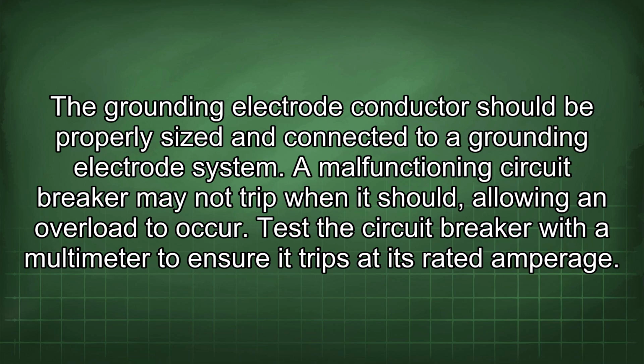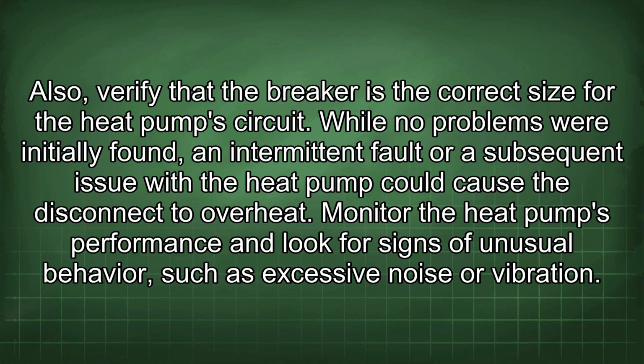A malfunctioning circuit breaker may not trip when it should, allowing an overload to occur. Test the circuit breaker with a multimeter to ensure it trips at its rated amperage. Also, verify that the breaker is the correct size for the heat pump circuit.